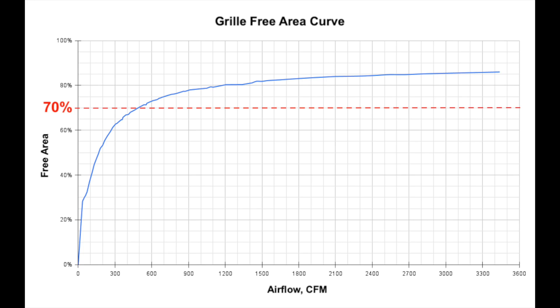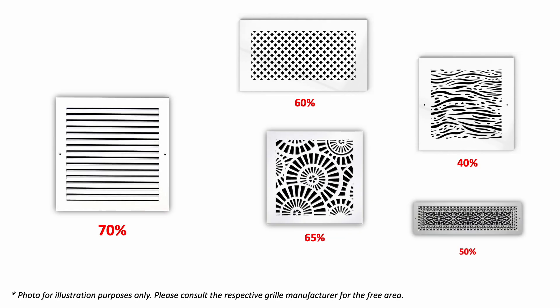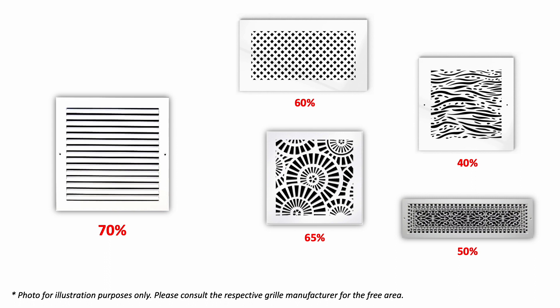However, the free area of the grill drops exponentially for small grills. Take a look at this graph. As you can see, the smaller the grill, the lesser the free area. So, when deciding what free area to use, you must account for the grill size as well as the pattern of the grill. A typical grill may have 70% free area, but if you have a very stylish grill, the free area may drop to 50%, so you need a bigger grill size to account for the smaller free area.